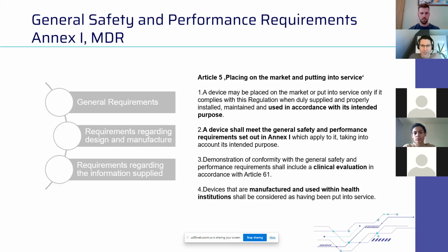A device shall further meet the general safety and performance requirements set out in Annex 1. So that's a shall requirement, which means this is non-negotiable. The only part is you can check each and every bullet and can state, this is not applicable to my product. But then you need an explanation of why you think this is not applicable, and then write it down in that checklist.